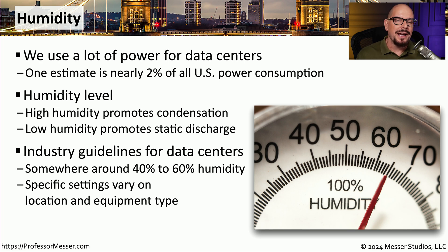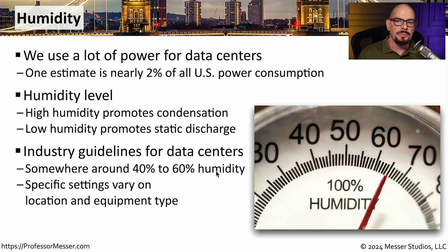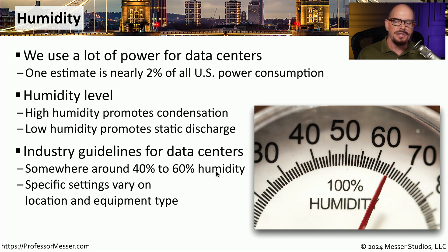Many industry guidelines put the ideal humidity levels somewhere around 40% to 60%. This is high enough to prevent any type of static discharge, but low enough to prevent any type of condensation. This can vary a bit depending on the geography, but these humidity levels tend to be the average you'll find in most data centers.